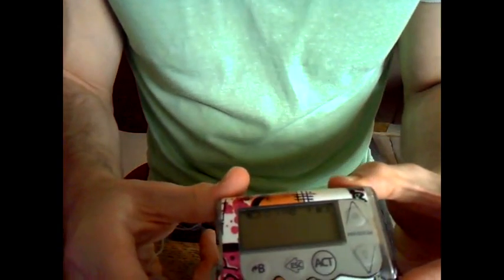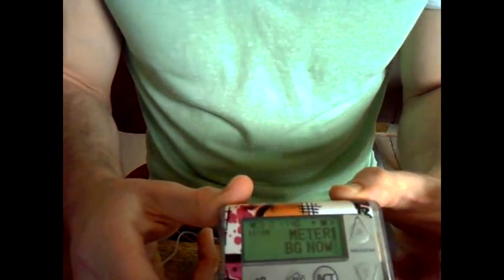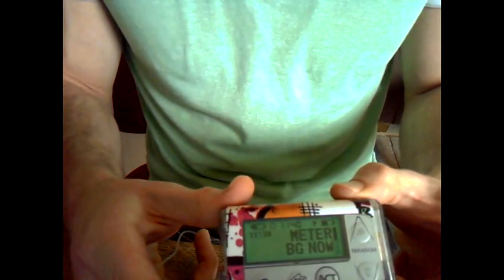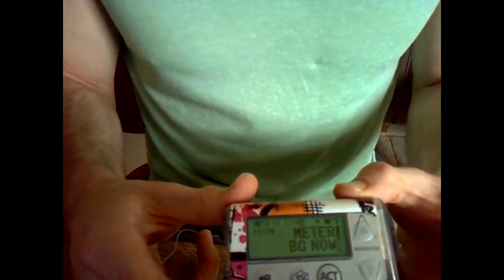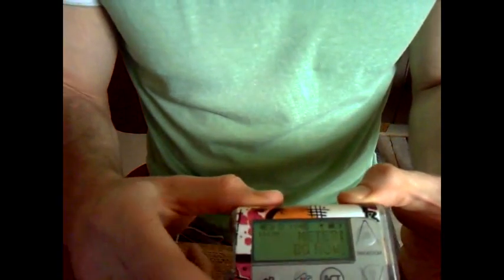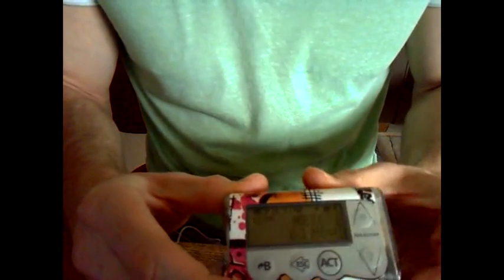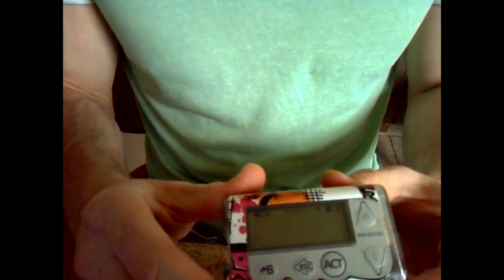This is fast forwarded 2 hours, and this is the message you would get now if it were 2 hours later: a message coming up saying meter BG now. And once you get that, to get rid of the alarm, you press the Escape button till it flashes, then press Act, and then you need to do a blood glucose test to do the first calibration. So I'm going to do mine now.